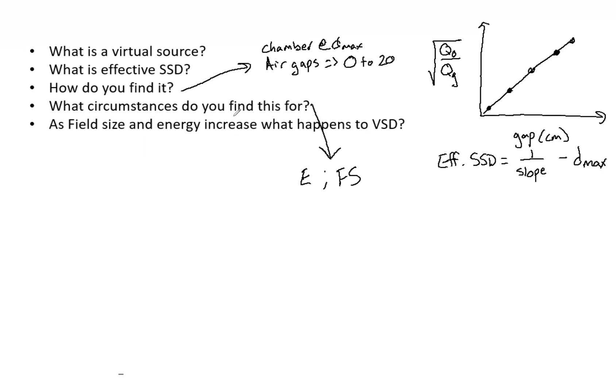So as field size and energy increase, what happens to the virtual source distance? If we have an increased field size, our virtual source distance is also going to increase. Similarly, as energy increases, our virtual source distance is also going to increase. So you only have to remember that if either of those circumstances happen, the virtual source distance is going to increase.